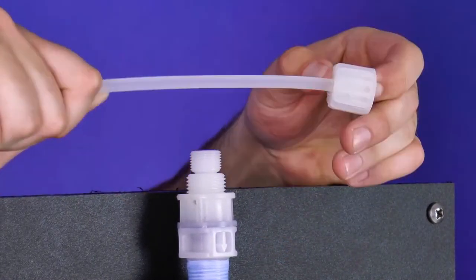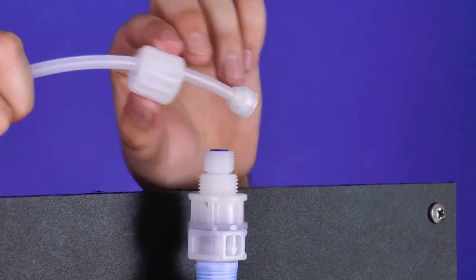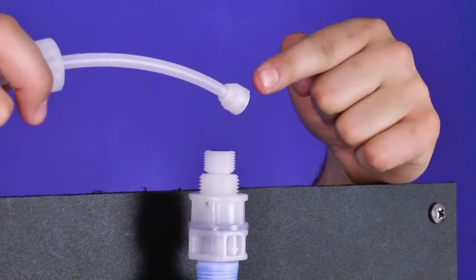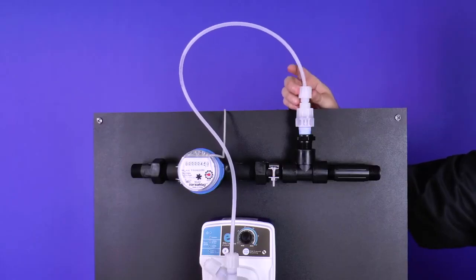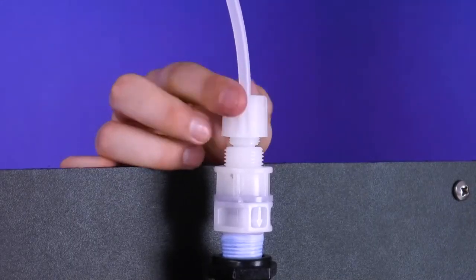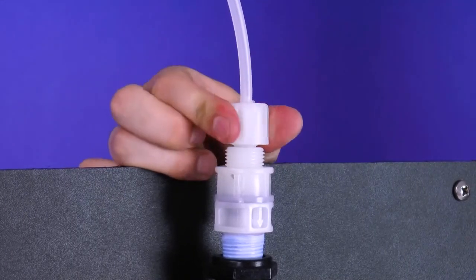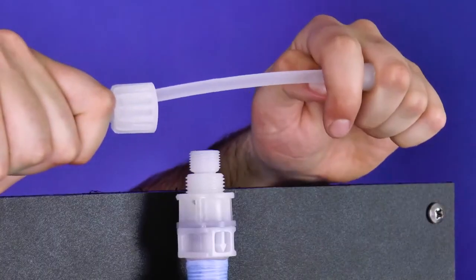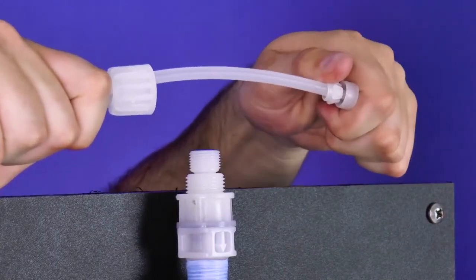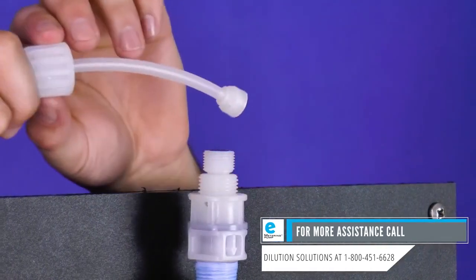Pull the tube nut toward the nozzle to compress the collar and nozzle tight together, forming a ferrule connection. Attach the tube and tube connections onto the injection valve by hand tightening the tube nut. Do not cross-thread nor over-tighten. If the tube nut is not securing, recheck the ferrule connection. Pull the tube nut toward the nozzle once more to compress the collar and nozzle together. Retighten the tube nut until secure.